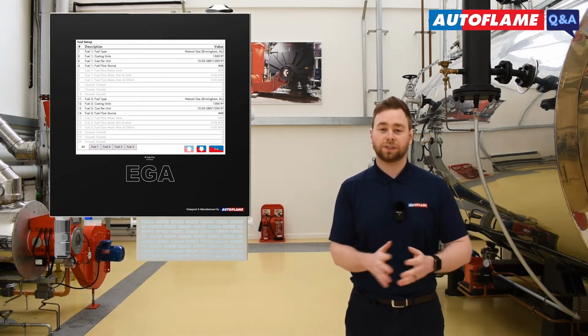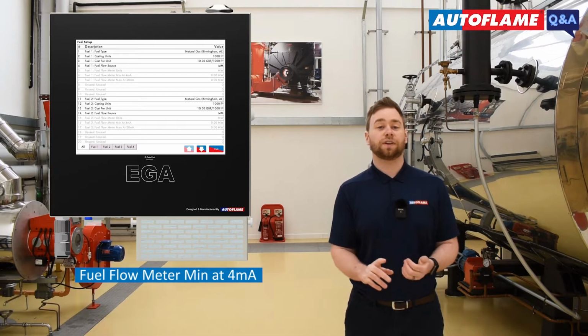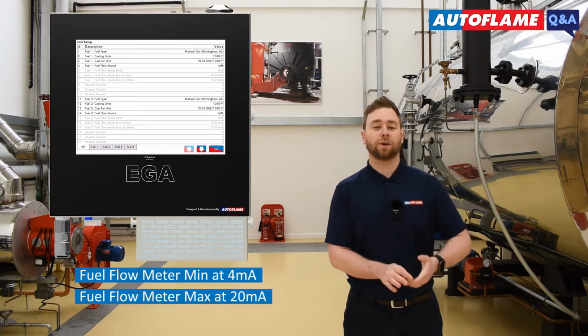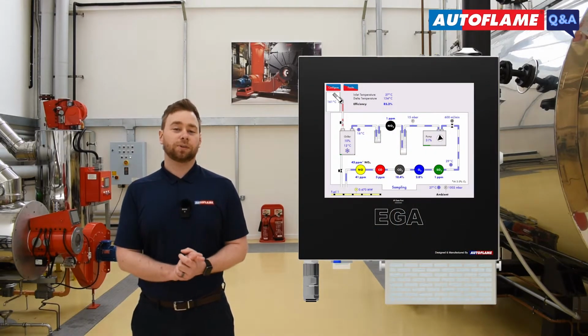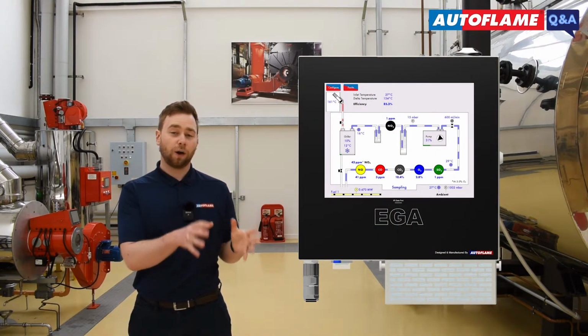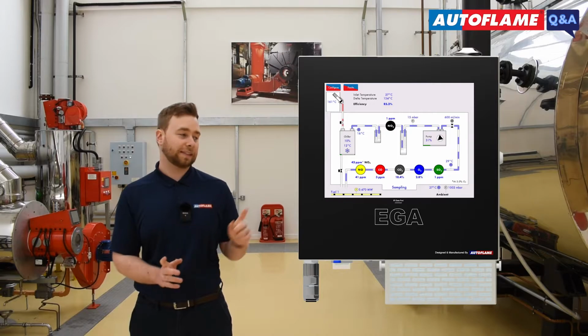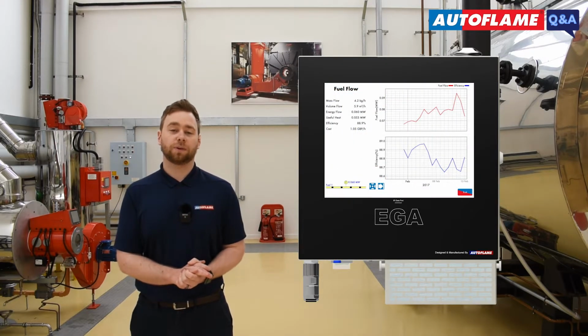Now finally, all you need to do is set up your scaling. So, your flow at 4 milliamp and your flow at 20 milliamp. Now we can see our real-time fuel flow data on the home page of the EGA. Simply tap on your fuel line to access your fuel flow screen.